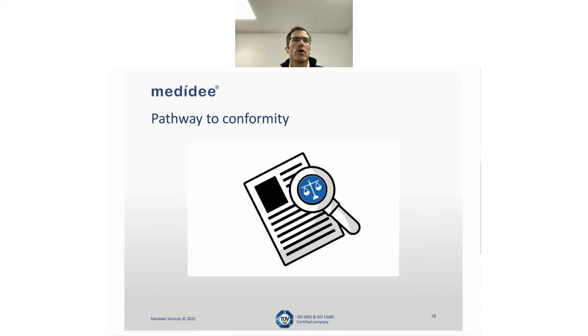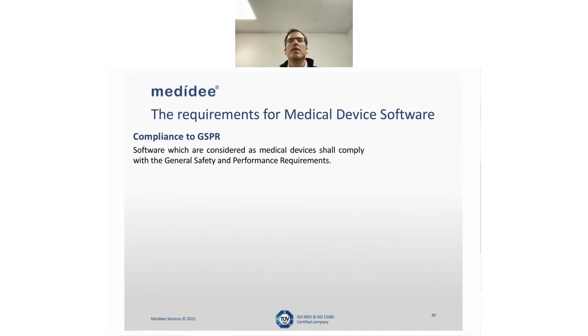The last topic I wanted to address was the pathway to conformity. So basically what you have to take into consideration when you are looking for conformity. As you have understood by now, the main approach is to be able to ensure compliance with those general safety and performance requirements, the 123 points that you find in Annex 1 of the regulation. And that's basically the driving approach for your way to conformity.